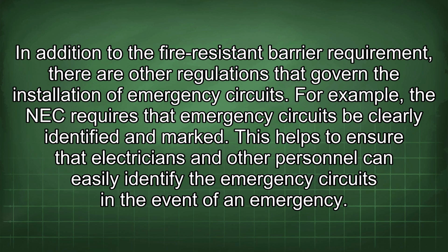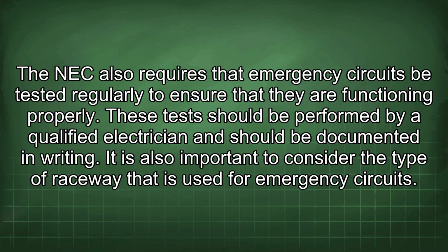In addition to the fire-resistant barrier requirement, there are other regulations that govern the installation of emergency circuits. For example, the NEC requires that emergency circuits be clearly identified and marked. This helps to ensure that electricians and other personnel can easily identify the emergency circuits in the event of an emergency. The NEC also requires that emergency circuits be tested regularly to ensure that they are functioning properly. These tests should be performed by a qualified electrician and should be documented in writing.